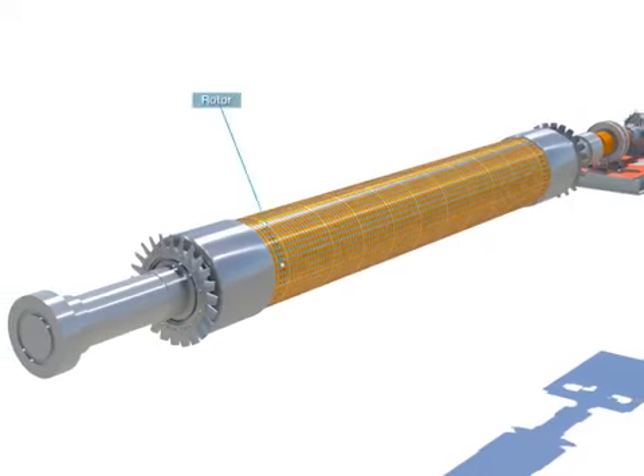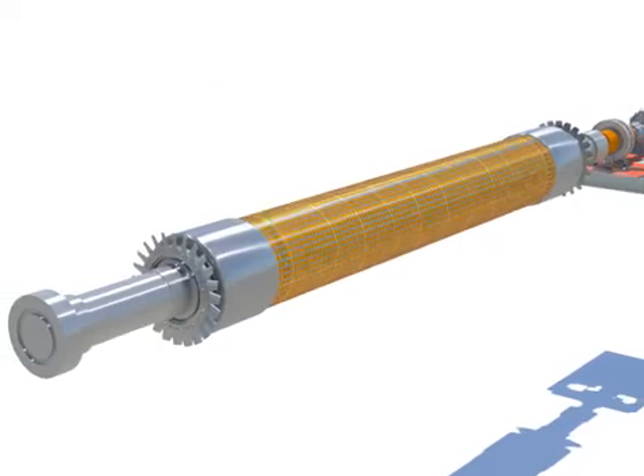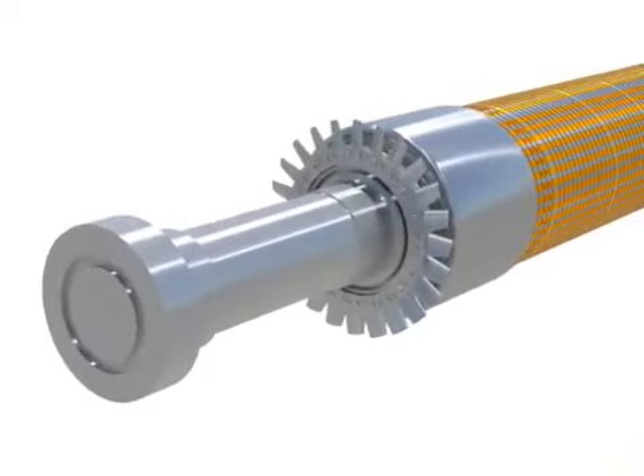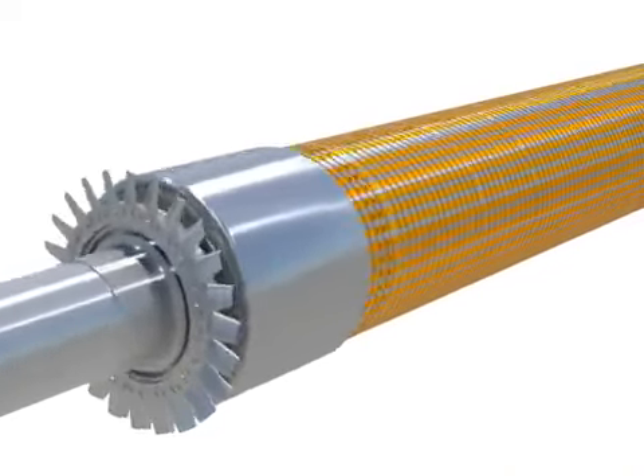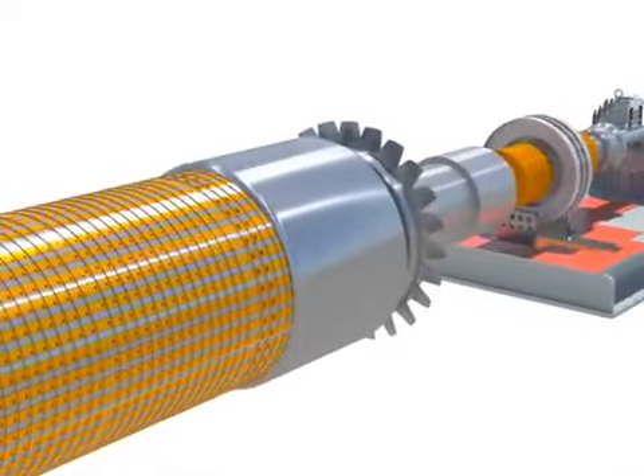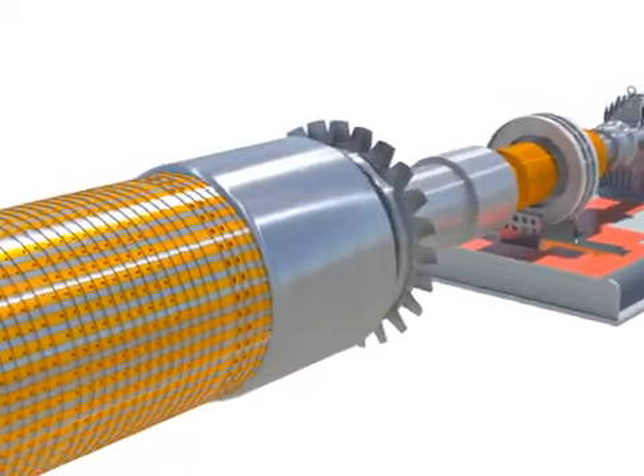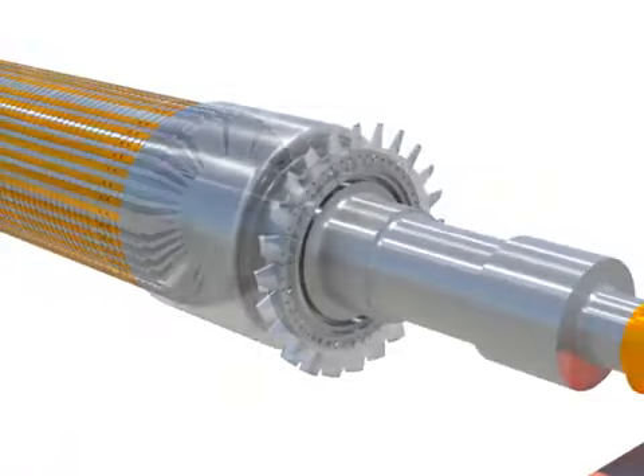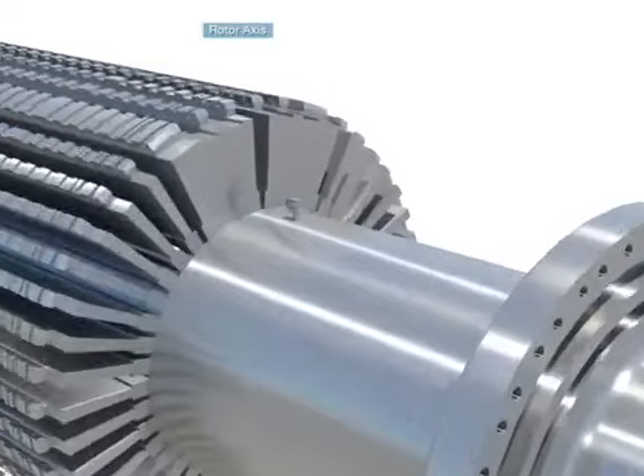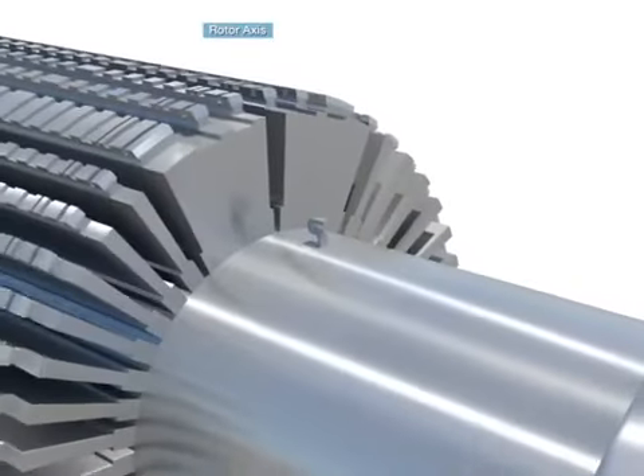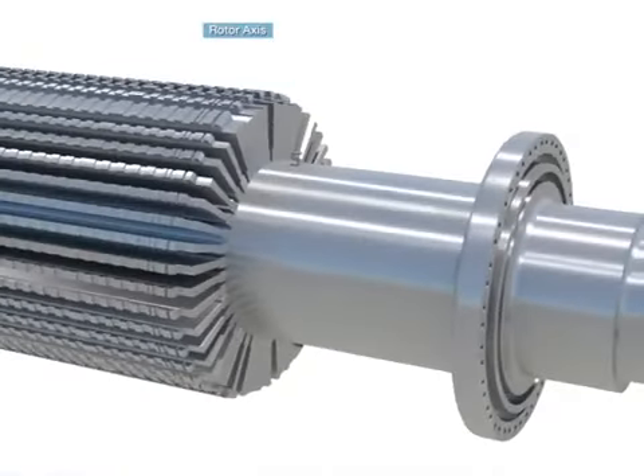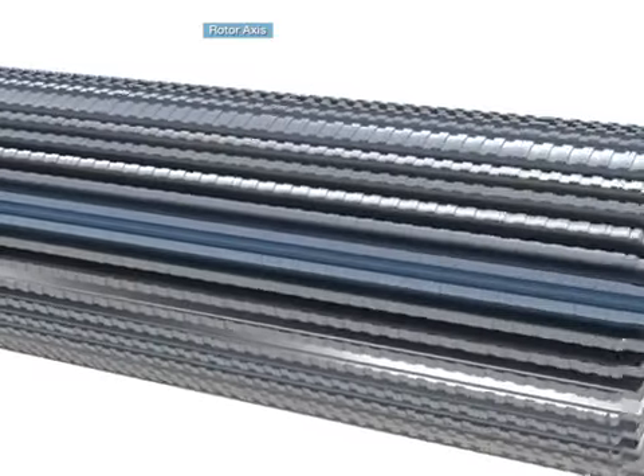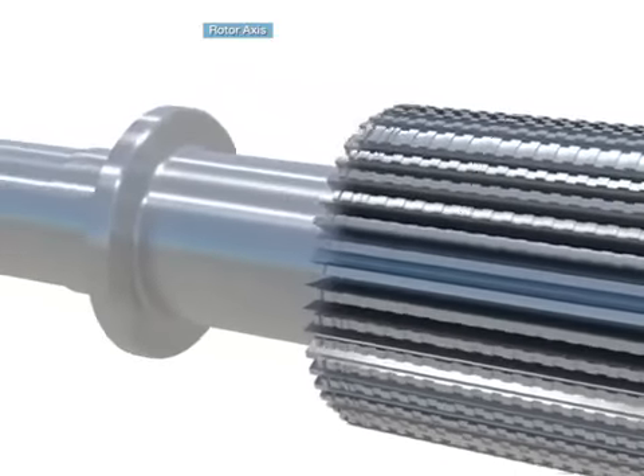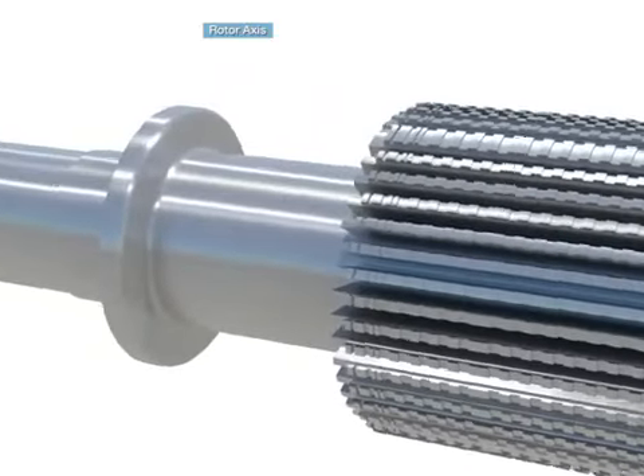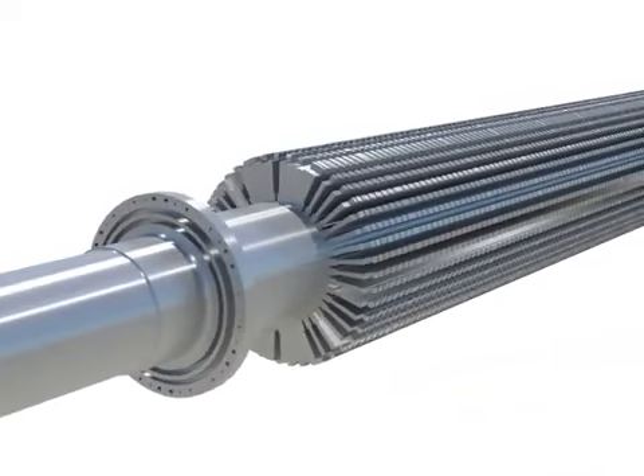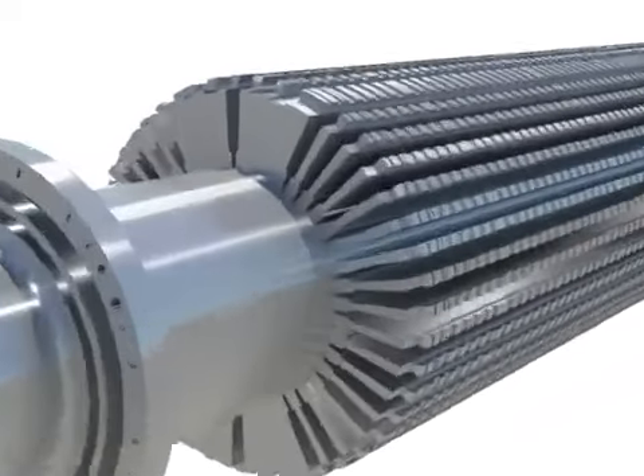The rotor is a part that spins around in a generator and provides direct current to the field winding in the exciter. The rotor shaft works as a support for the field winding and makes a slot in the core part and inserts the rotor winding. At the center of the shaft, there is a hole to examine inside flaws with a bore scope.